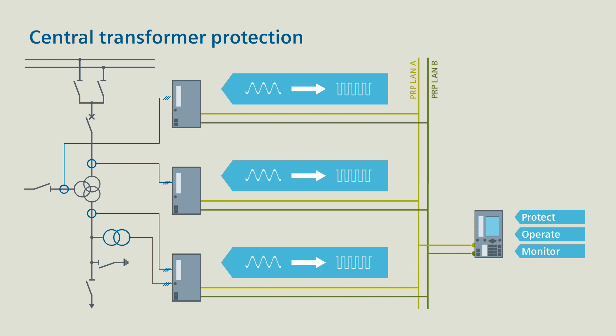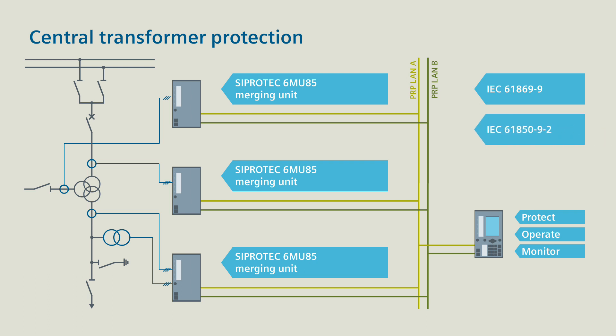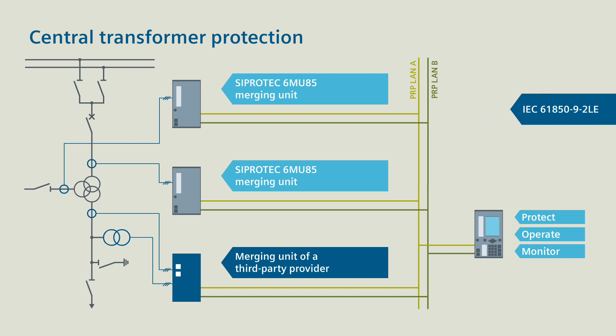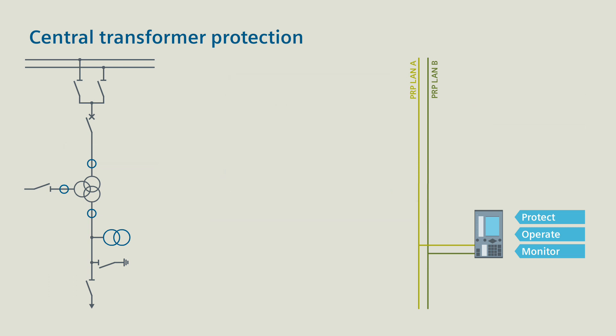With SIPROTEC 6MU85 merging units, the digitalized measured values can be transferred in compliance with the IEC 61869 Part 9 and IEC 61850 Part 9-2 standards. When the merging units of other providers are used, you can shift to the IEC 61850 Part 9-2 light edition standard if required.